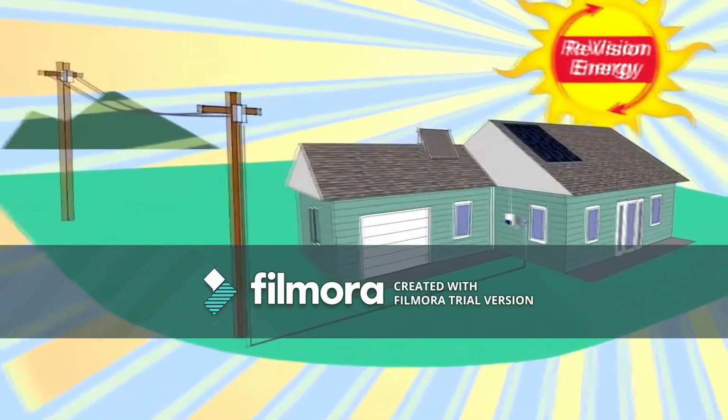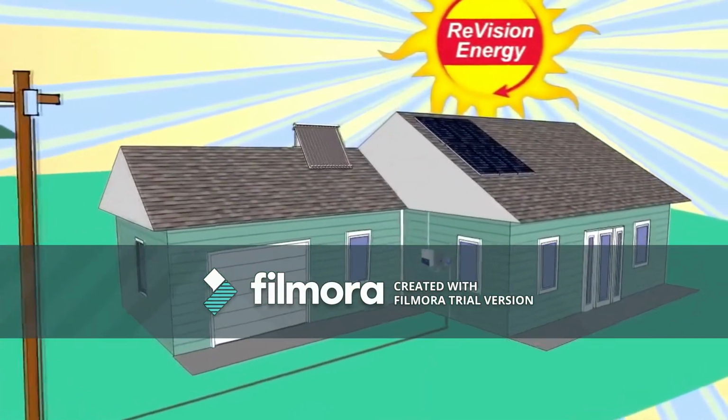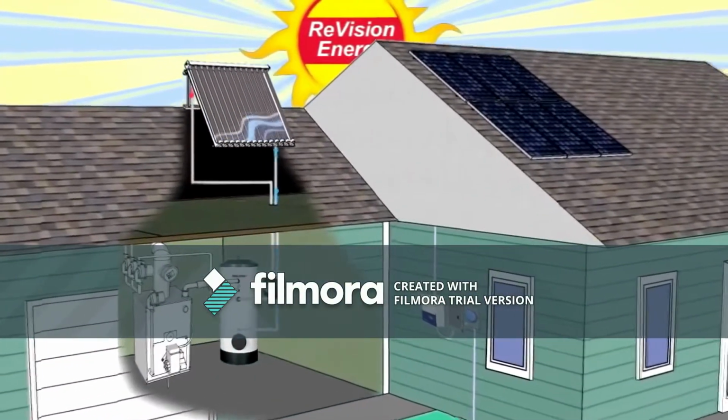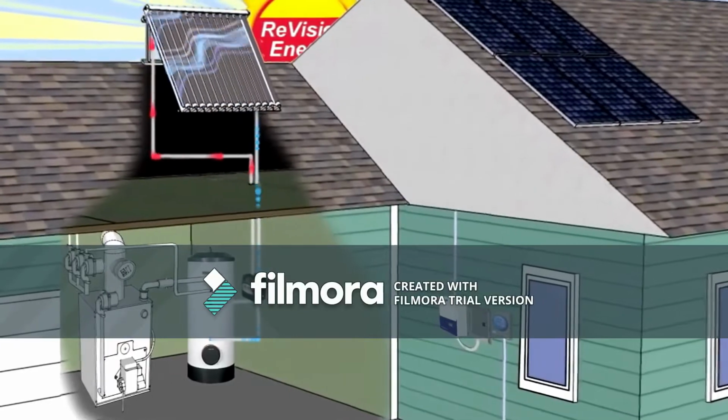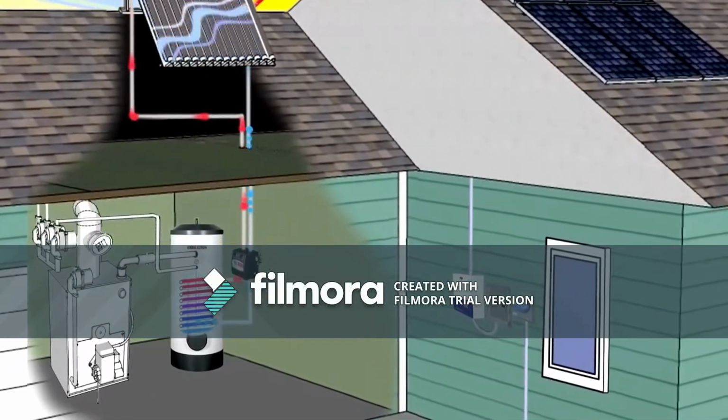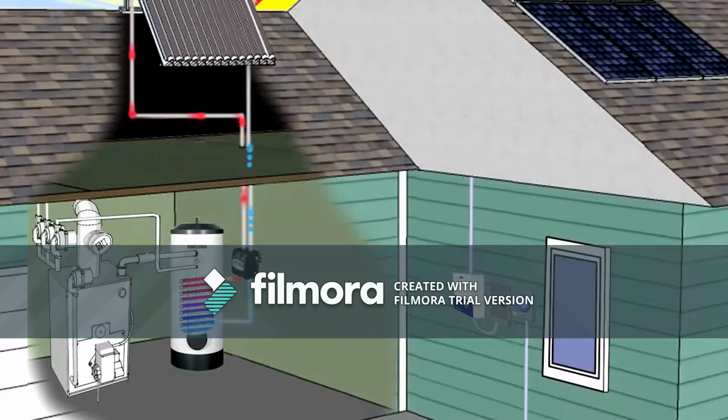Solar hot water takes the sun's heat and turns it into usable thermal energy. When the collectors on your roof are warmer than your water tank, a differential temperature controller then activates a pump. This pump then circulates a non-toxic antifreeze mix up to the solar collectors on your roof, where the fluid heats up. The solar heated fluid is then pumped to a super insulated storage tank, where it gives off its heat as it passes through a heat exchanger. It's then pumped back to the roof to continue the cycle as long as the sun is shining.